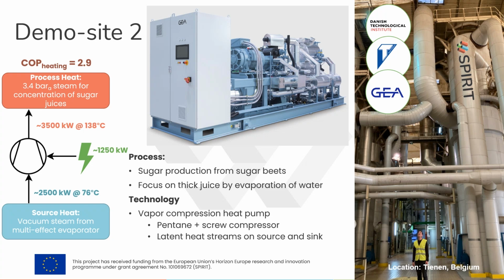One of the main challenges we have with this site is that we have a latent heat stream, which is in the form of vacuum steam on the low temperature side of the heat pump. That means we have large volumes, and we need very big heat exchangers in order not to have too high pressure drops and temperature drops on the source heat side.